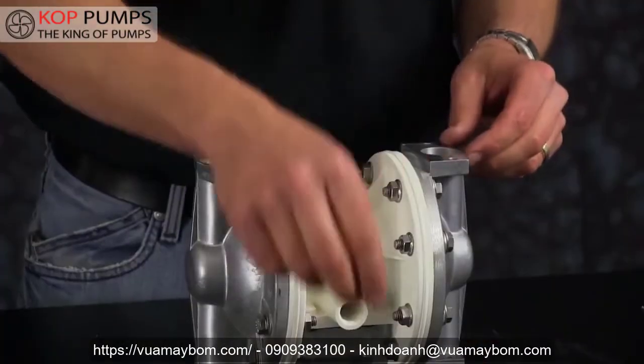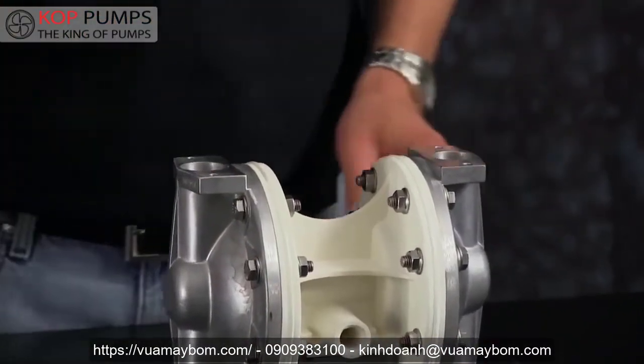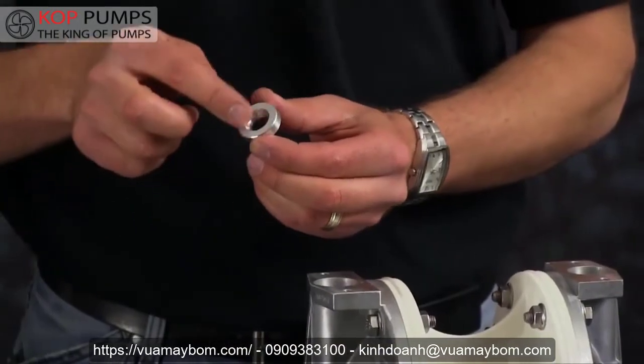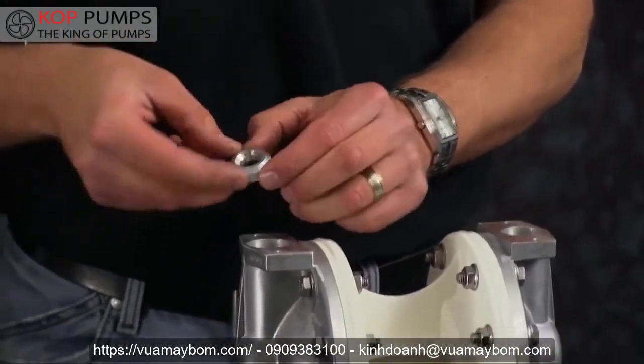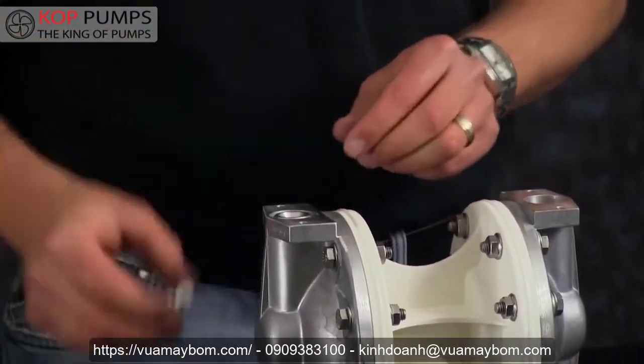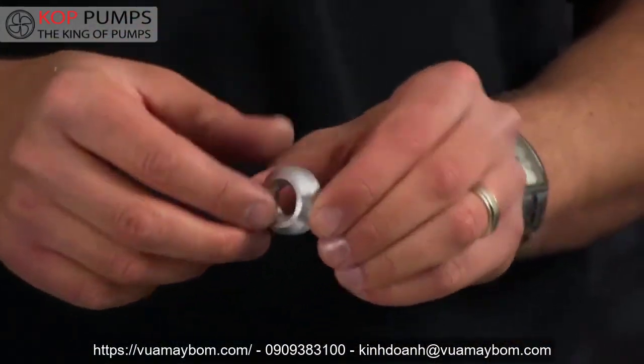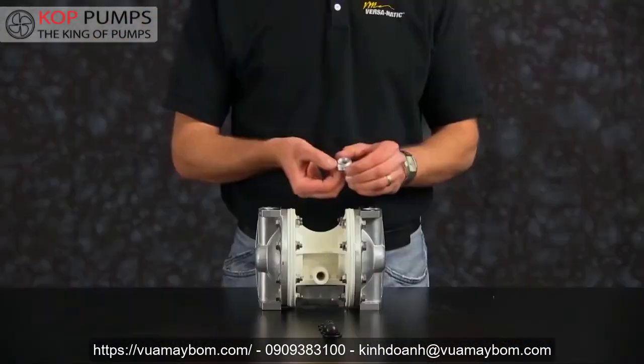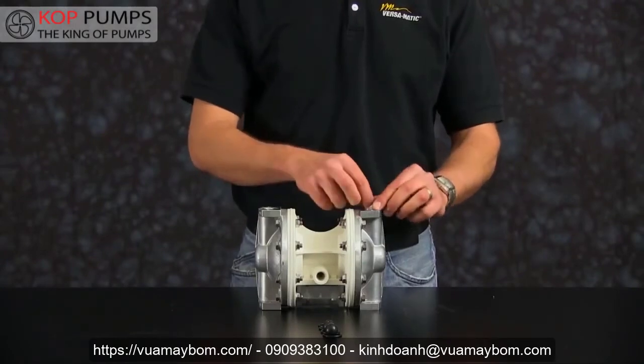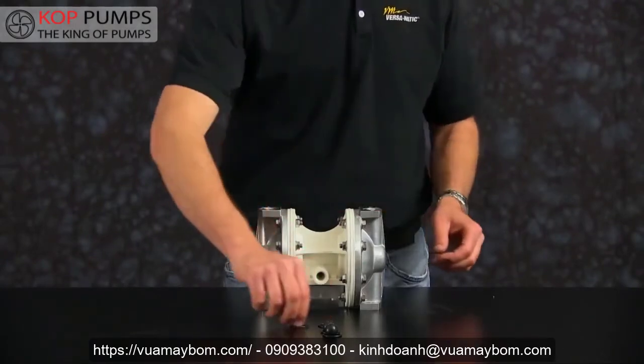Now we're ready to install our suction side check balls, our valve seats. Inspect the valve seats for any wear or damage, replace as needed. The chamfered side of the valve seat will face towards the suction manifold, and install the valve seat O-rings.